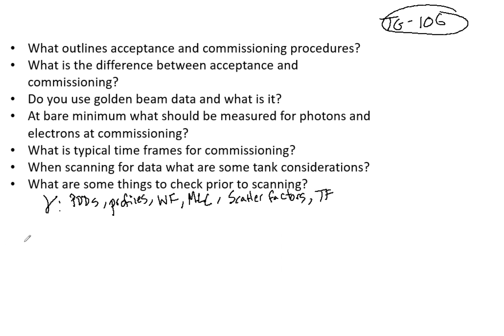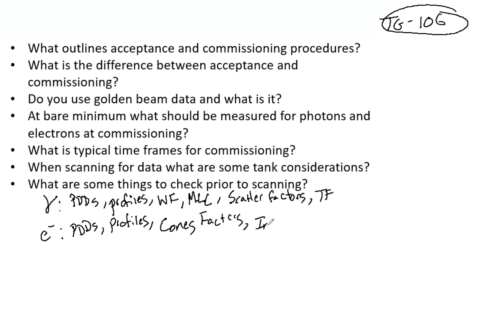For electrons, you similarly need percent depth doses and profiles — both in-plane and cross-plane. Since electrons use cones, you need cone factors as well as applicator or insert factors, because different applicators produce changes in output when the field size is not the reference 10x10. You also need the virtual source position. Those are the bare minimum measurements needed for both the photon and electron beams.